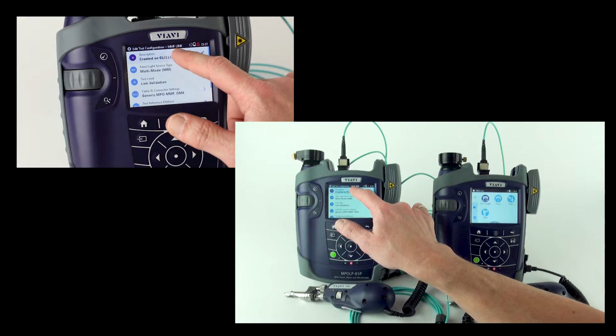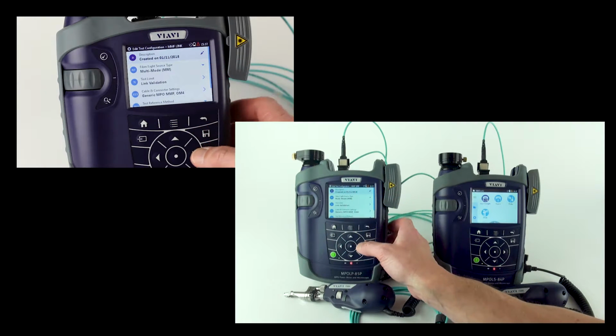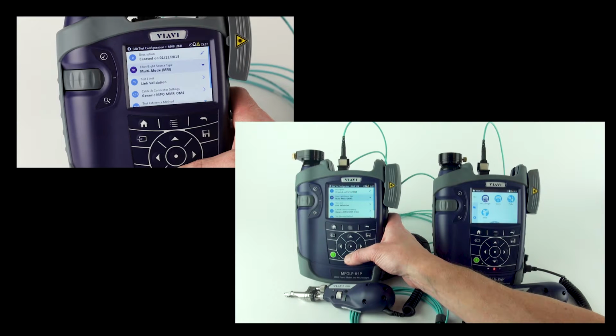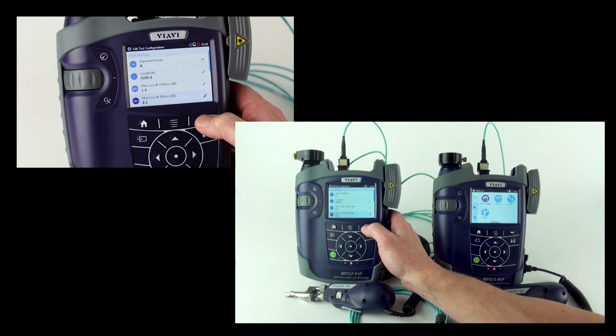So I'm editing the test configuration, which is called MMF link, and it tells me when it was created. I get to choose my source type, whether I'm connected to a multi-mode or a single mode source. I get to set my test limit. In this case, I'm using a link validation test limit, which means that I have to enter in dB values for the two wavelengths that I tested. For multimode, it will be 1300 and 850. I have to tell it what polarity, that's why the polarity check is useful, and I have to tell it the maximum length before it will cause a fail. Then I have my 1300 wavelength, what is considered a pass or a fail for it, and the same with the 850 nanometer.